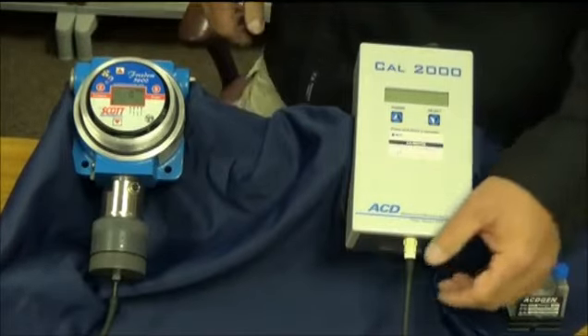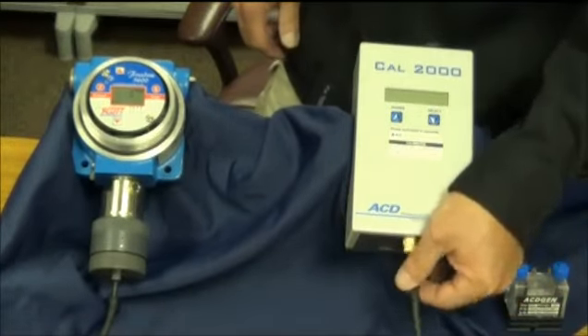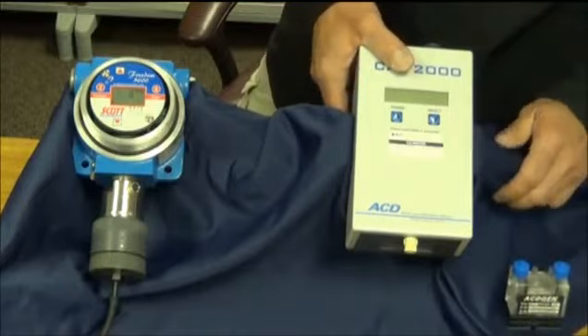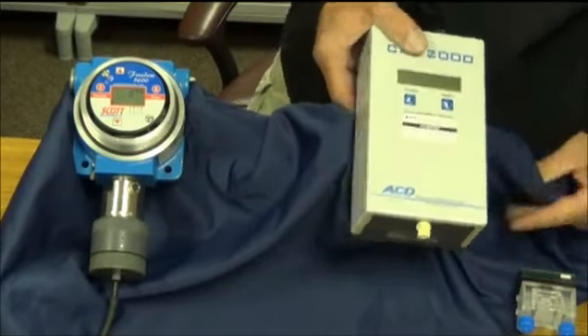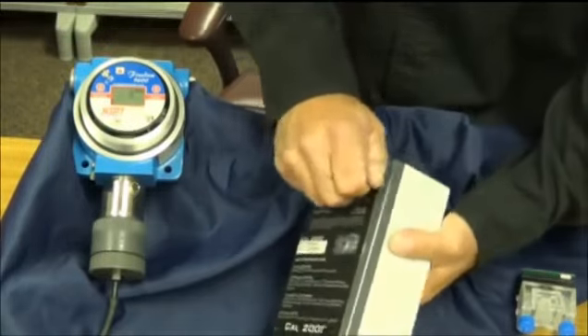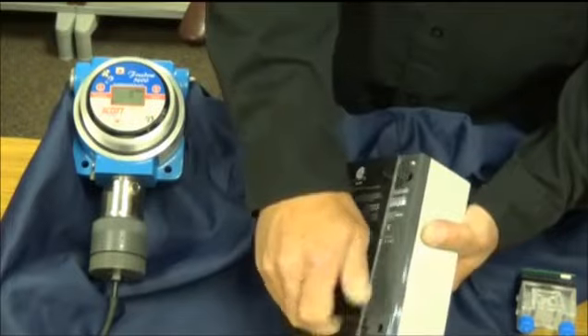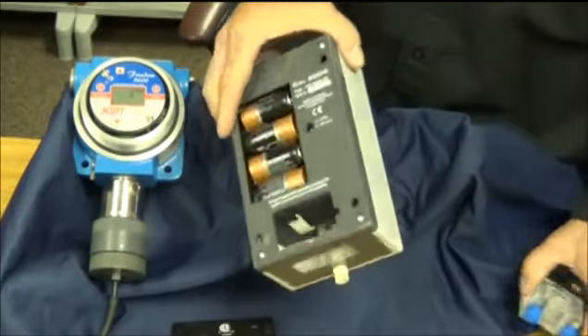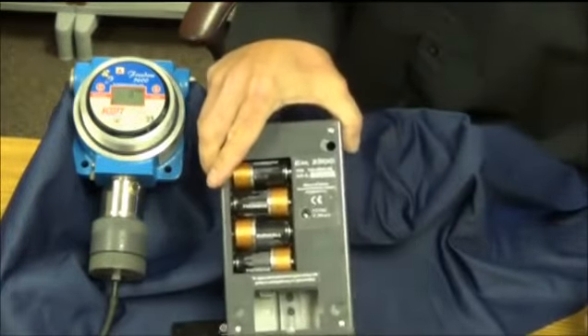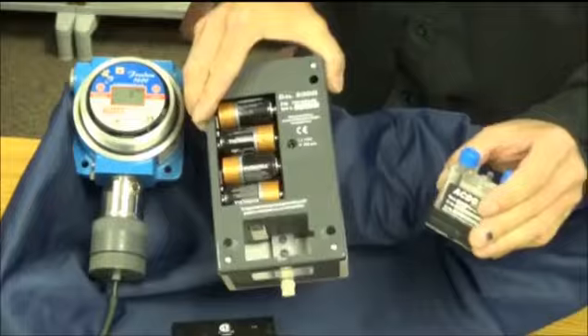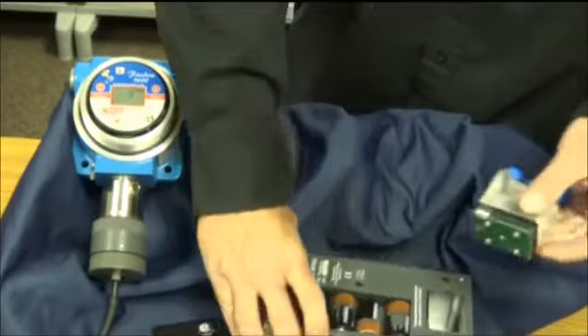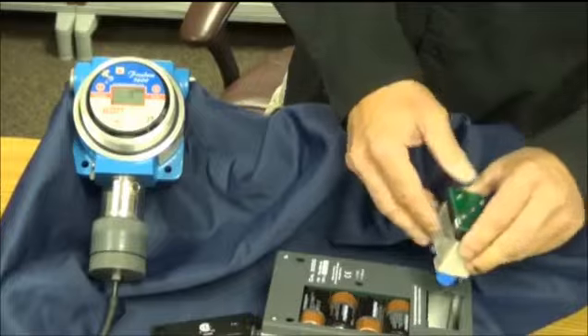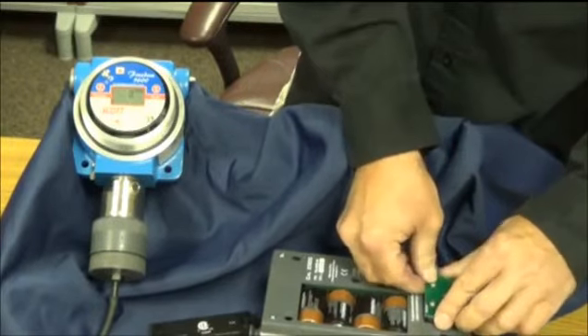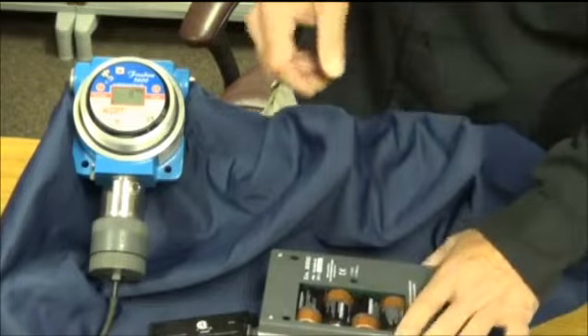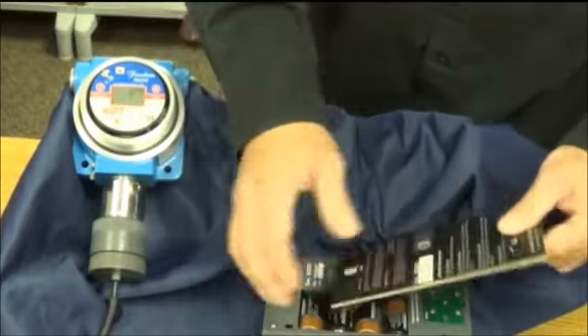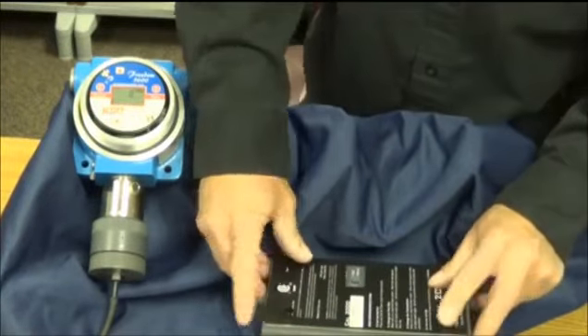The first thing we need to do to calibrate this gas monitor is to put the generating cell inside of the instrument. This is an H2S Scott brand sensor, and so we're going to put an H2S generating cell inside the instrument. As you see, the Cal 2000 runs on 4 C batteries. This is the generating cell. It's got 4 male pins that insert into a ribbon connector in the instrument. You line those up. It's keyed so that you can't put it in wrong. You place it in the instrument and then you put the cover back on.